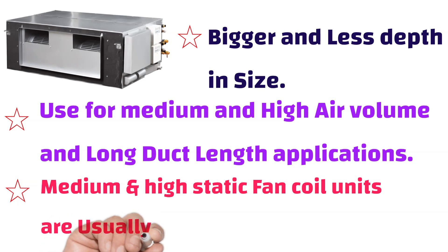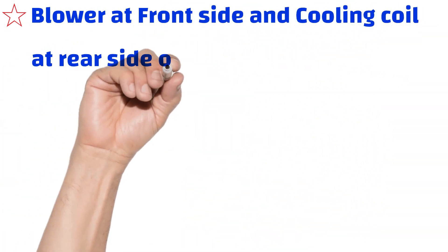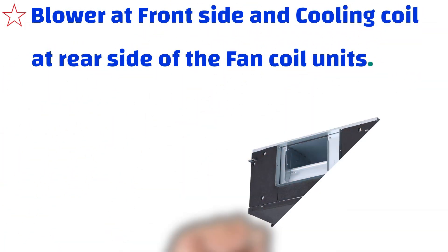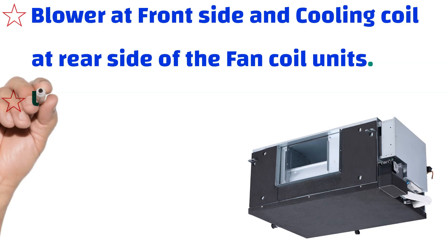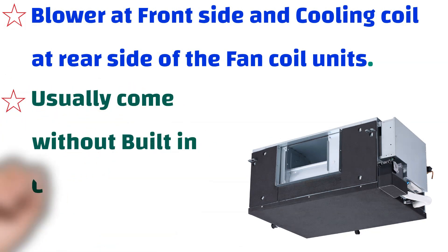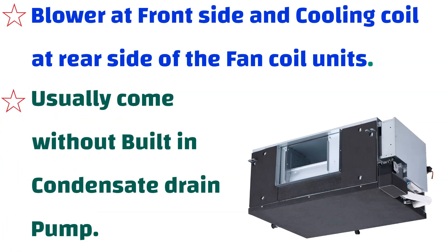Three, medium and high static fan coil units are usually a draw-through unit. Four, blower at front side and cooling coil at rear side of the fan coil units. Five, usually these units don't come with condensate drain pump.